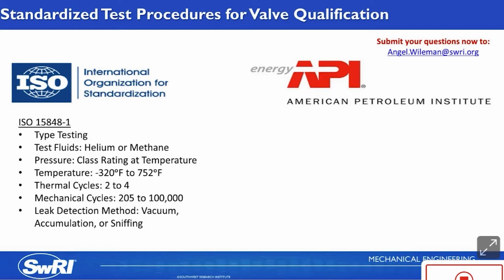And the number of mechanical cycles ranges from 205 to 100,000 cycles, depending on the endurance class and also whether the valve is intended for actuation and service as a control valve, or if it's an isolation valve that will remain closed or open for the majority of the operation. Obviously, control valves are intended to be actuated, so they must undergo significantly more mechanical cycles to qualify. And the external leakage measurement methods for this standard are either a combination of the vacuum method, the accumulation or bagging method, and the sniffing method.